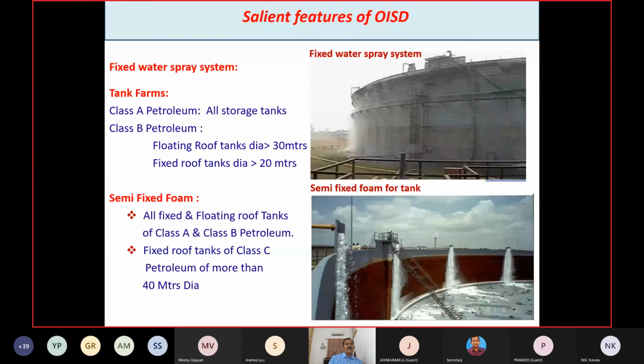Fixed water spray system. It should be provided for all storage tanks of Class A petroleum, Class B petroleum and floating roof tanks having more than 30 meters diameter, and fixed roof tanks of more than 20 meters diameter. We should provide a fixed water spray system.